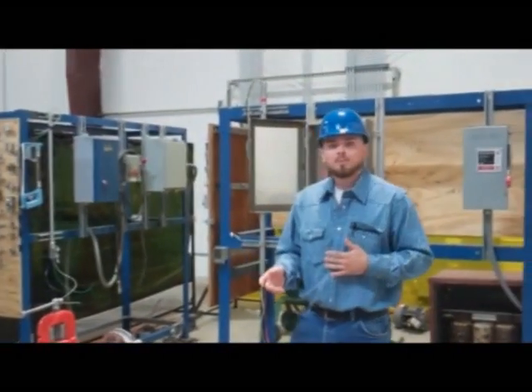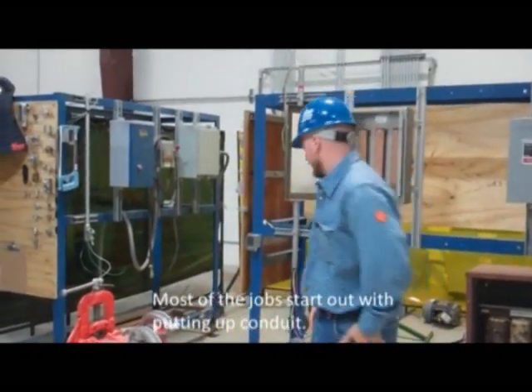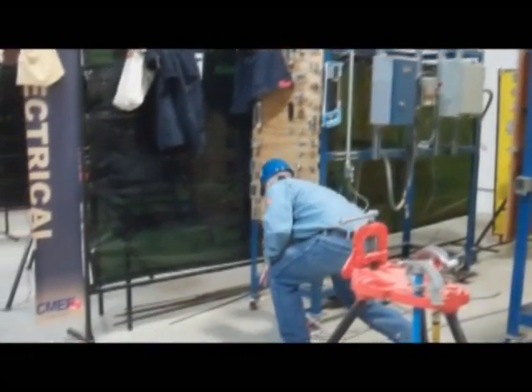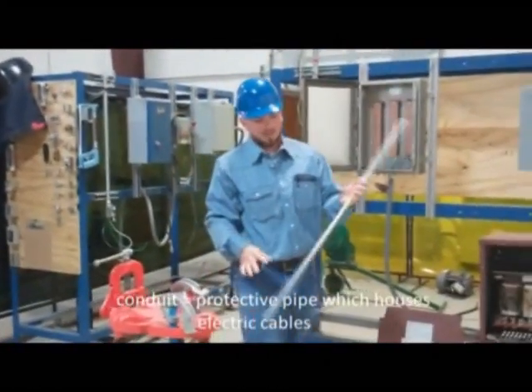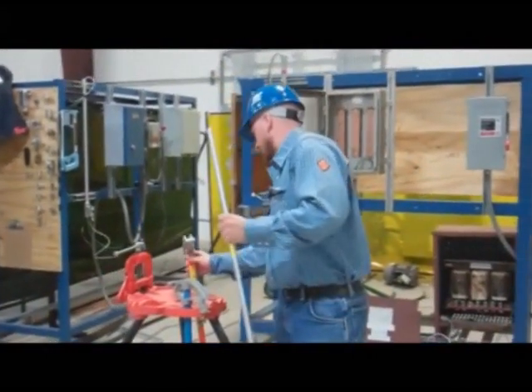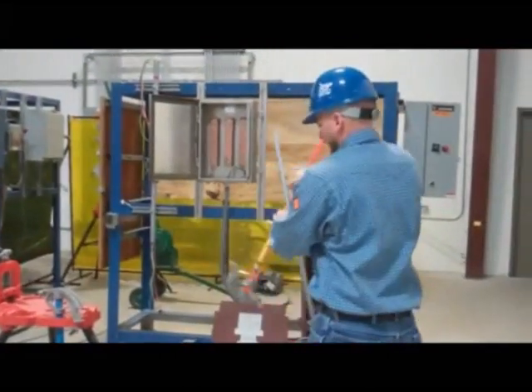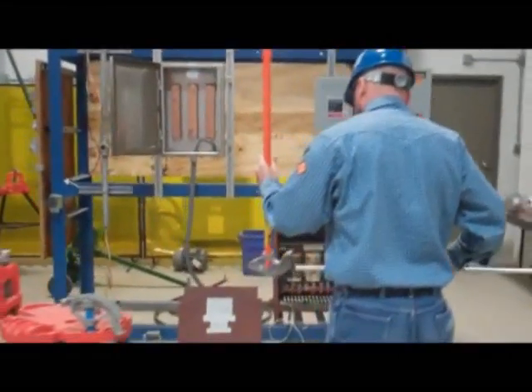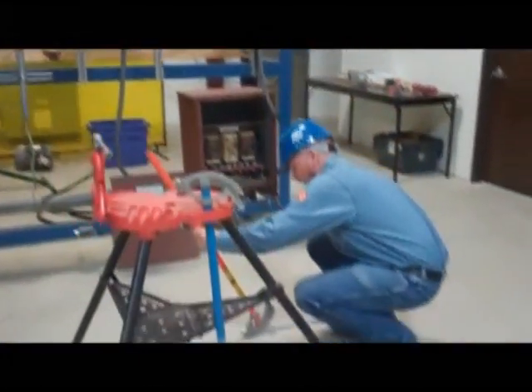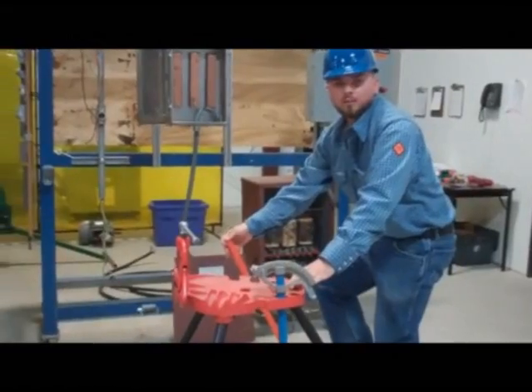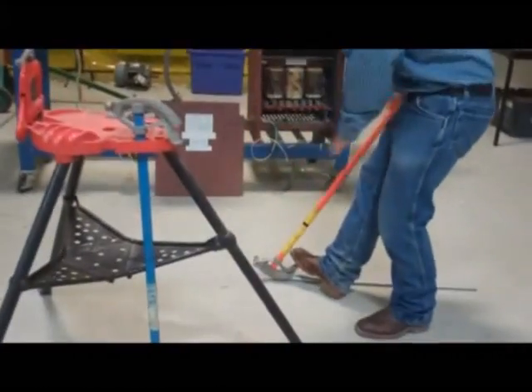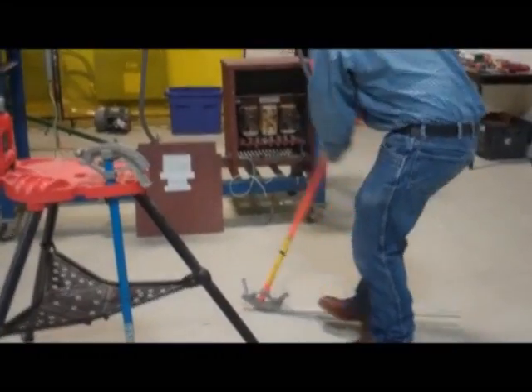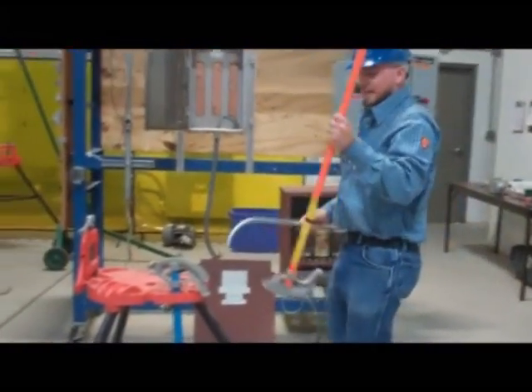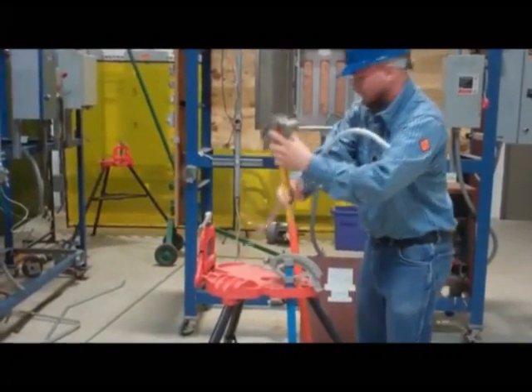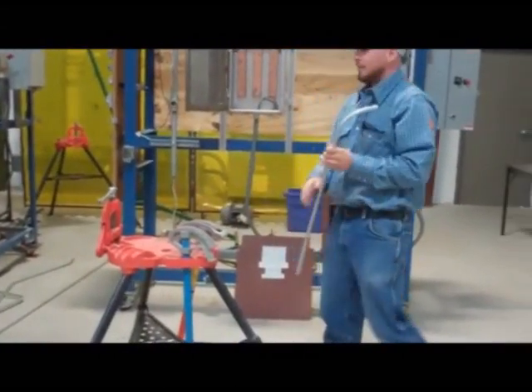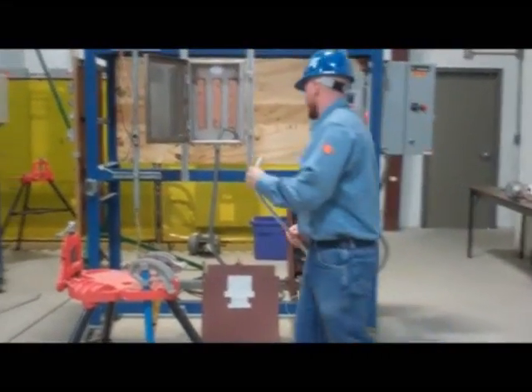Well, most of the times, jobs started off, we put up conduit. So, we got all sizes of conduit. Not everything's going to look just like this. This is EMT conduit. Most times you see this inside buildings or housing. And this is a 90-degree piece of conduit. When you run a conduit, you need to get somewhere.